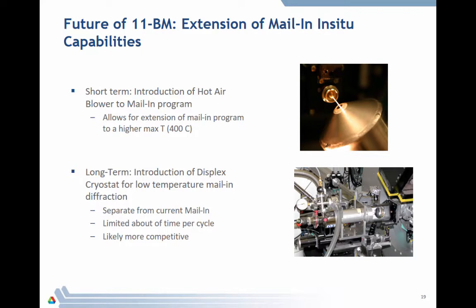Let me now talk about some of my future plans for 11-BM, particularly plans I have for extending the mail-in program, because I believe the mail-in program is kind of one of the unique strengths of 11-BM. In the short term, we're introducing a hot air blower to the mail-in program, which will allow us to extend the temperature range that we can measure. We will be limited to roughly 400°C, because in the mail-in program we use Kapton capillaries. And above that, you get softening of the Kapton, and so going higher is not an option.